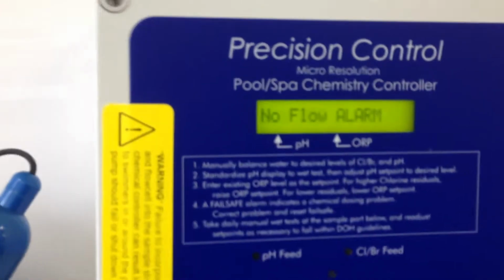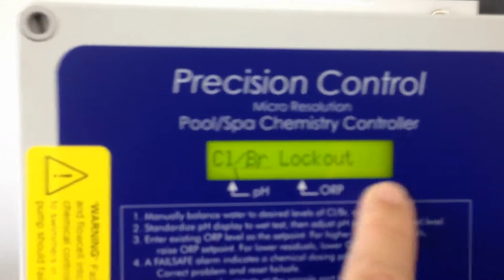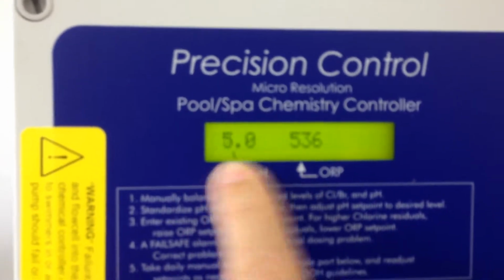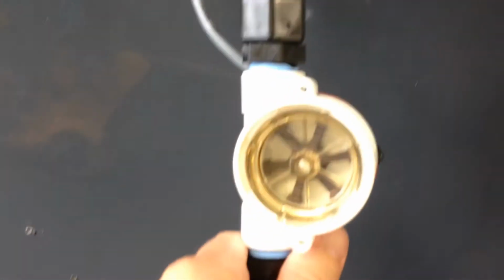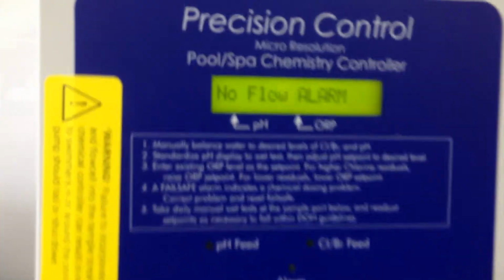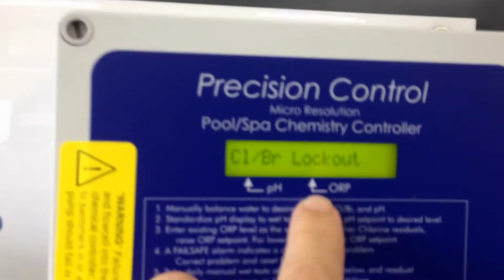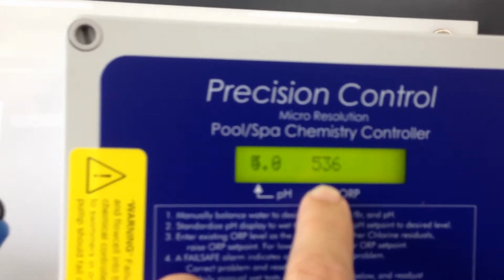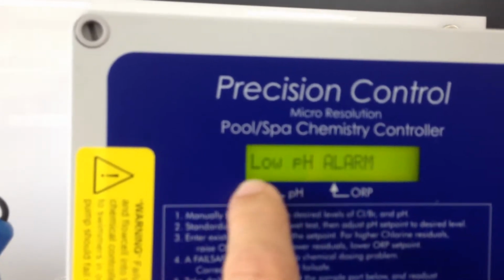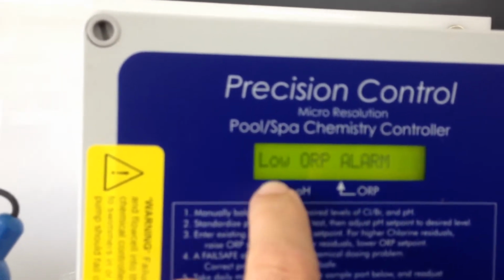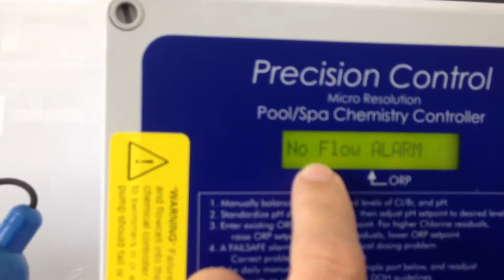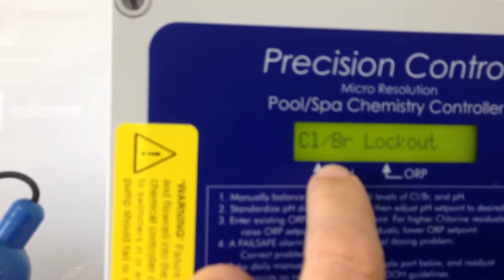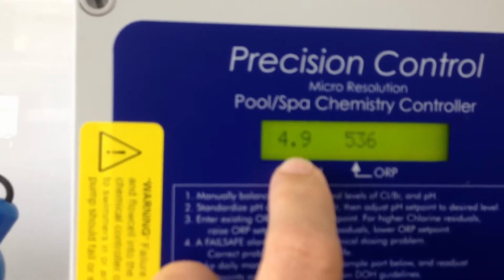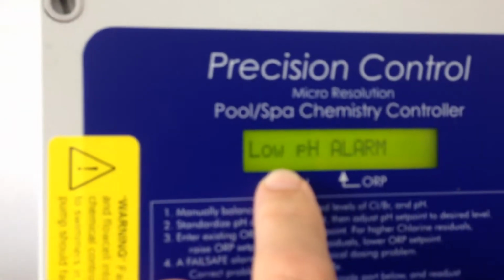You pay attention also to these alarms. For example, the no flow alarm is obvious because we're not turning anything. The low ORP alarm is obvious because we have a set point and the ORP without any water running through it is 536. The low pH alarm is obvious because we don't have any water running through it, and it's showing a 4.6 pH, which is a lot less than the 7.5 that we want to hold.